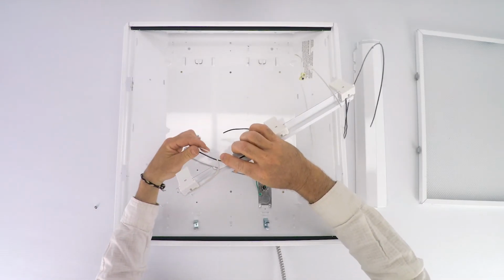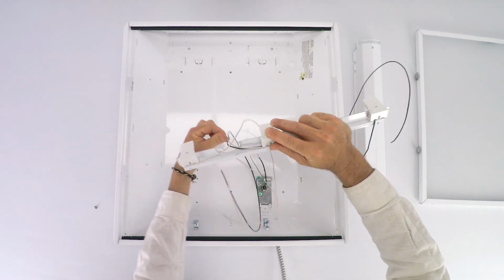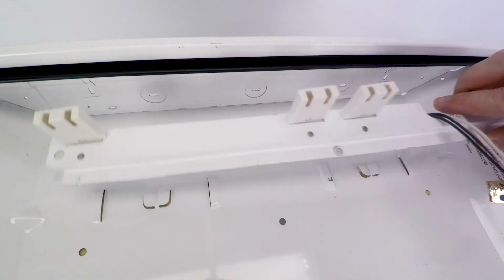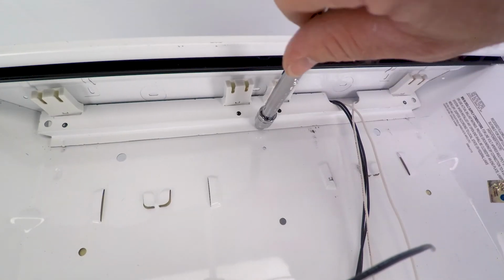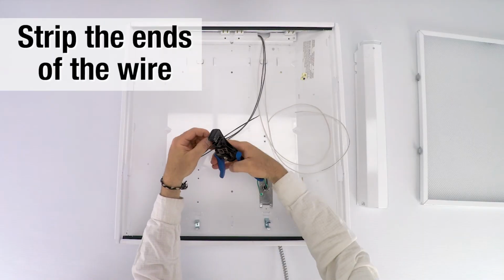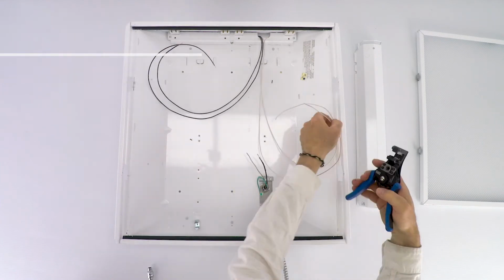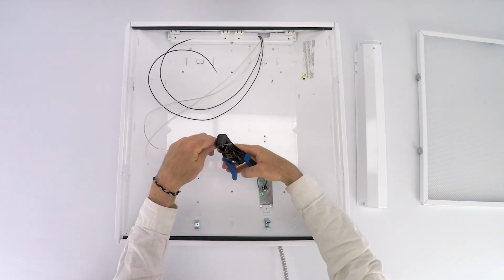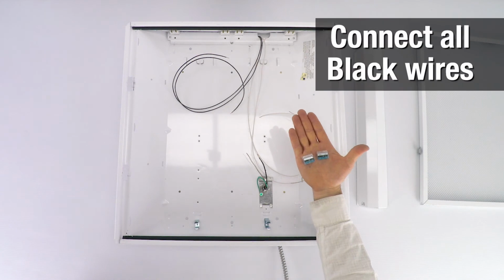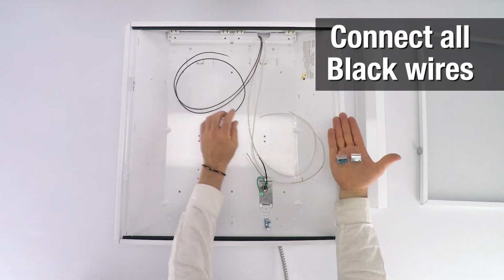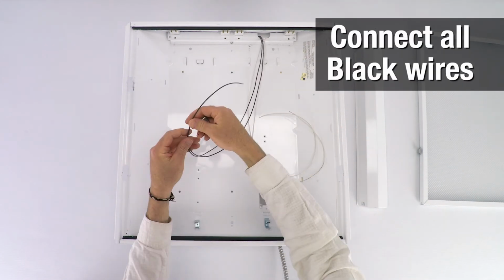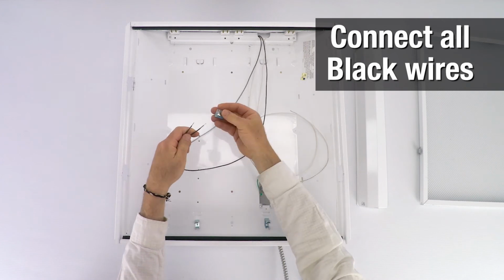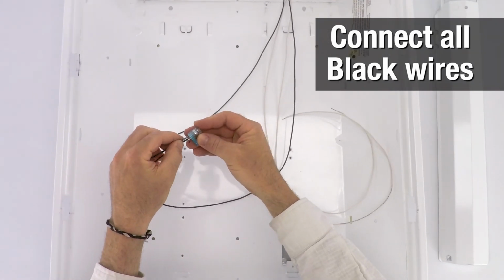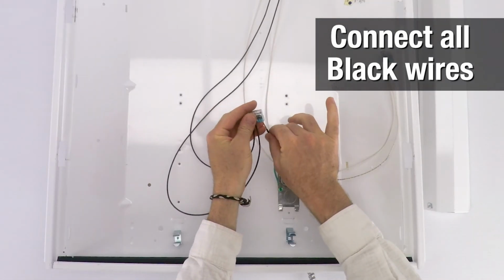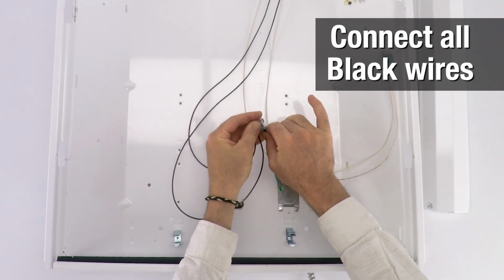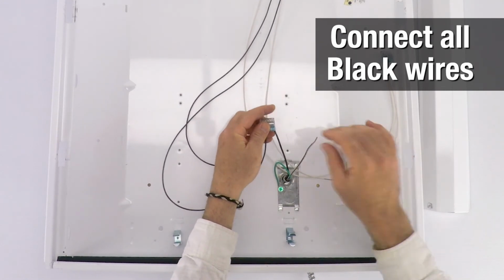So once you got the plate in and it's all set up, make sure the wires aren't pinched. You don't want pinched wires, and you don't want anything causing a problem later. Then, very simply, we're going to connect all the black wires into this little quick connector. So all the black wires in the fixture, all the hot wires get joined together. So the hot wires from our sockets and the hot wire coming into the light fixture that's supplying power all get connected with this little port.